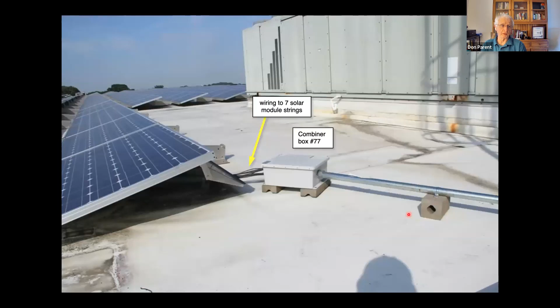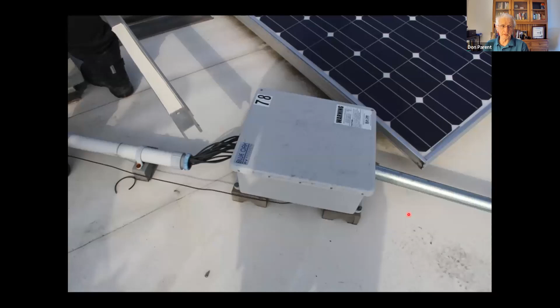Here you see a picture of a combiner box, and you see 7 of the module strings coming into the combiner box. Each one of those wires that you see there, we'll look at a little. Here's another one. This is a different combiner box, but it's the same thing. Seven wires are bringing approximately 7 to 8 amps of current into this combiner box. The code requires that all of those wires be in conduit, but they were not. We just saw 2 that were like this, and there are like 81 combiner boxes on the roof, so it's likely there are others in this same condition.